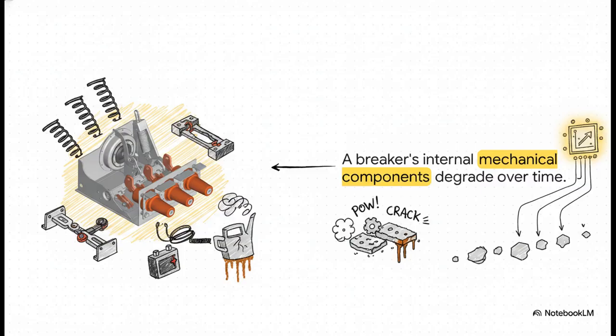Looking at this breaker mechanism cutaway, you can really see the physical reality of what we're dealing with. A breaker's rated mechanical life might be specified for a strict 10,000 operations, or a maximum number of fault interruptions at its rated current. You've got heavy springs, linkages, moving contacts, energy storage mechanisms, the whole shebang. And every single time this thing operates, it undergoes mechanical wear and tear. Over months and years, friction goes up, lubricants dry out, parts wear down. But the absolute beauty of modern digital relays is that all of this mechanical wear can be continuously monitored electronically.